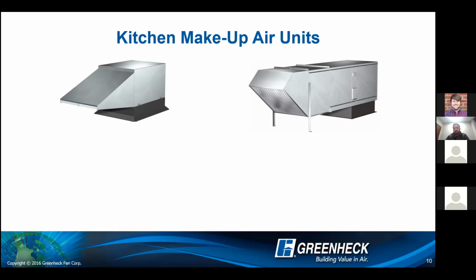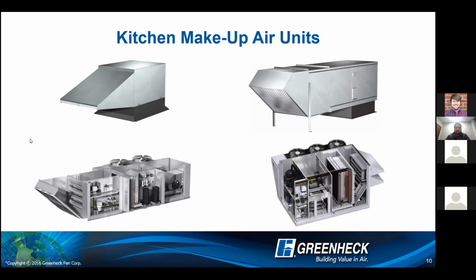When we're talking about design considerations and the current state of kitchen ventilation design, we're going to touch on why you temper air and what the question to tempering makeup air in a kitchen is. But just know that Greenheck has the product, no matter the situation, to provide your makeup air. So we have our untempered units, our direct fired heat only, so our DGX makeup air units. And then Greenheck also offers the package DX, split system DX, our heat and cooling options, as well as our DOAS units, or our RV or our RVE unit, which again, we're going to go into the design considerations behind DOAS a little bit further on in this conversation, but Greenheck has the product offering to meet all your needs.